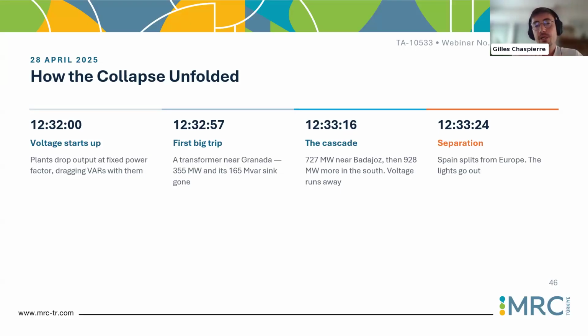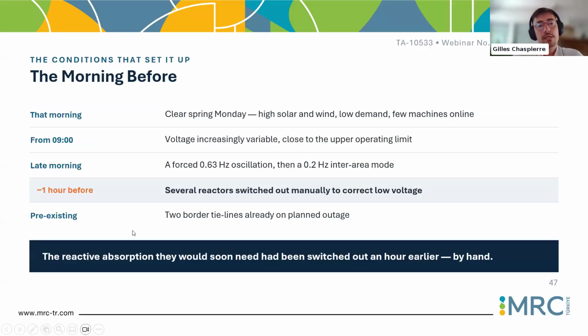But it's really the first big trip. So first big trip, meaning it was a transformer that tripped because of protection, over-voltage protection, that has led to the loss of MVAR capability. But MVAR, when you are in an over-voltage situation already, is so important to keep the voltage control below this critical threshold that if you lose some, you start having trouble. And that's really what happened. You have the first big trip, then the cascade, then the separation. Yeah, we can go to the next one.